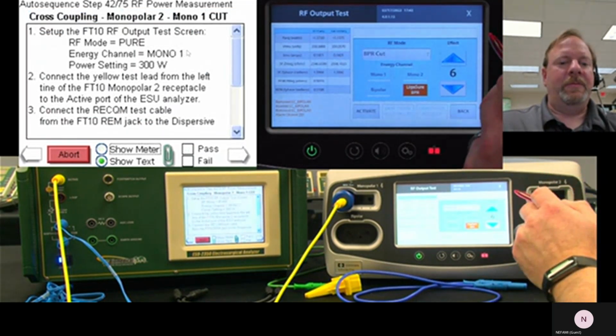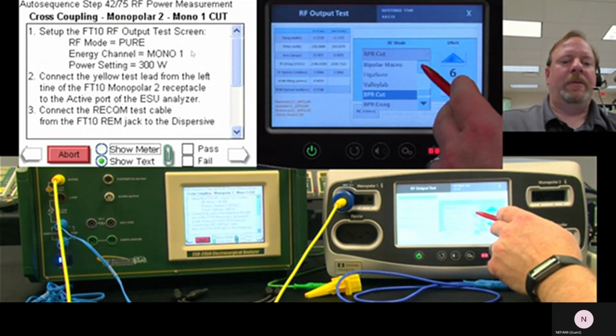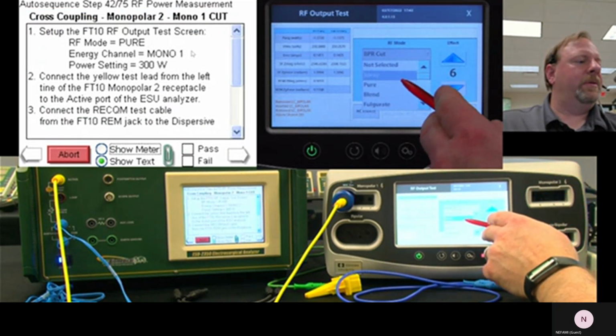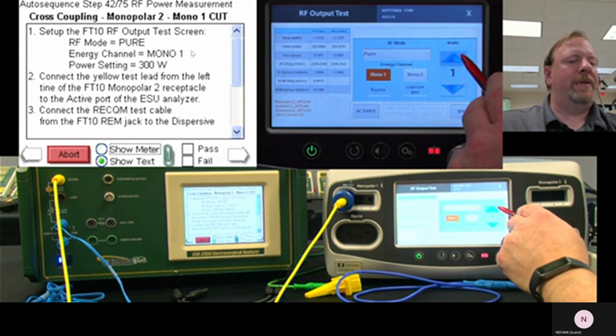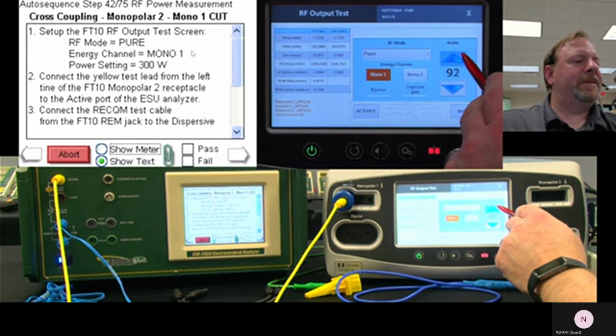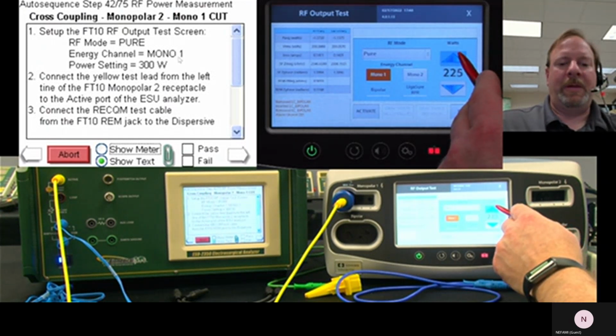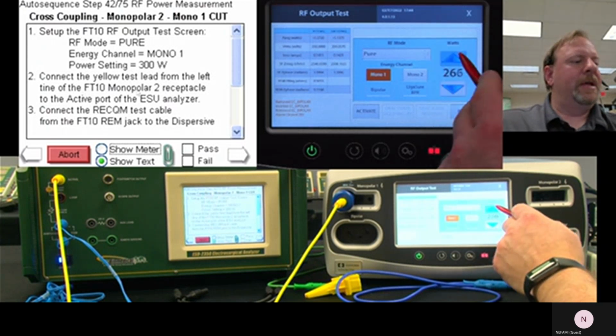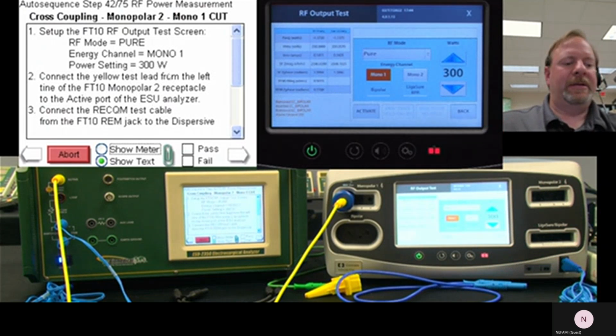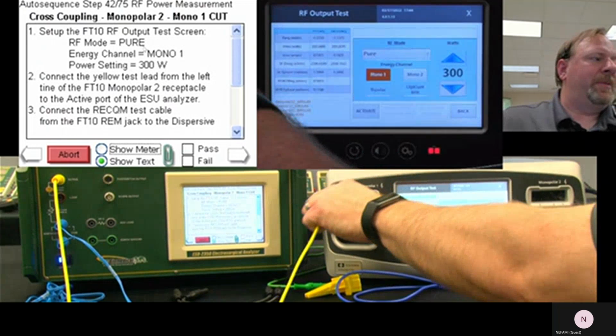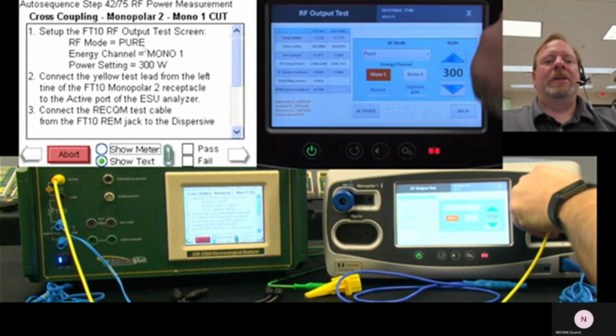Then we go to monopolar 1. Going to pure cut, maximum power. We're still in cross coupling. So since we're activating monopolar 1, we're probably connecting the monopolar 2. So that's some of the keywords as you run through this to help you make sure you've got the thing set up right. You see the cross coupling at the top. We're activating monopolar 1. So if we're activating monopolar 1 and we're doing cross coupling, we can't be connected to monopolar 1.